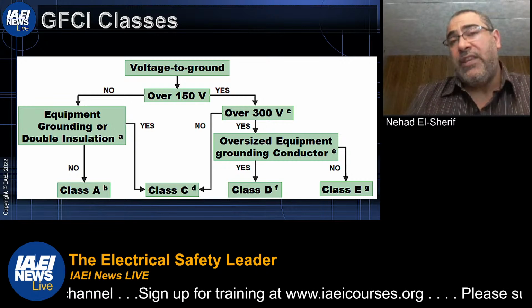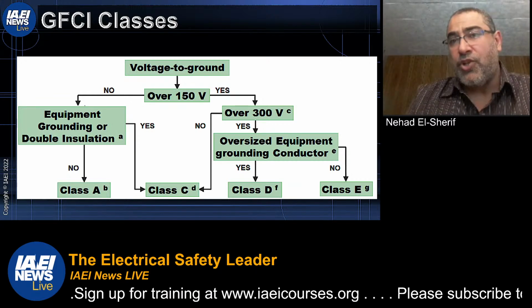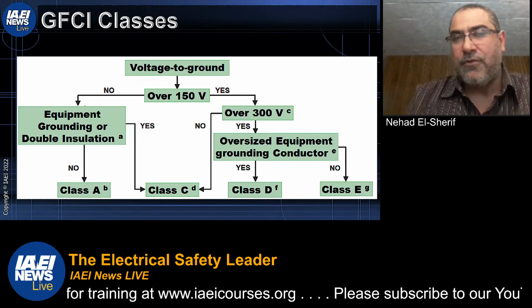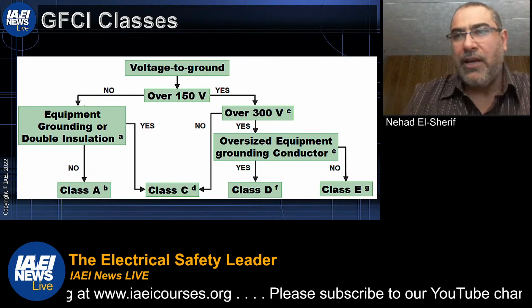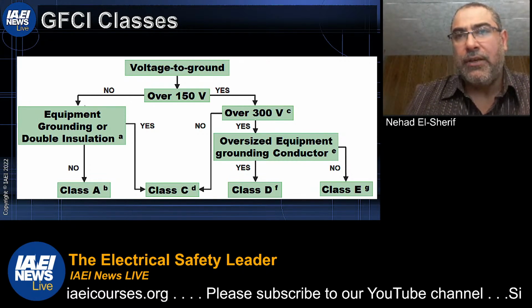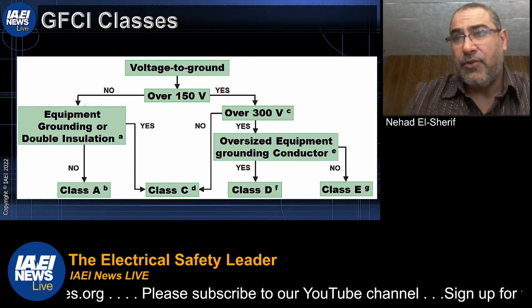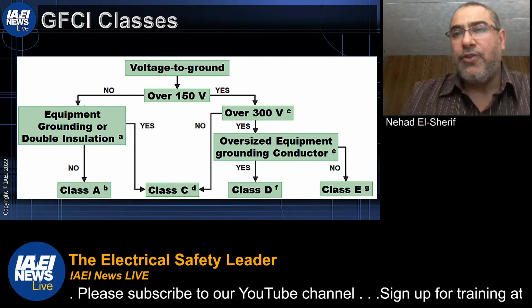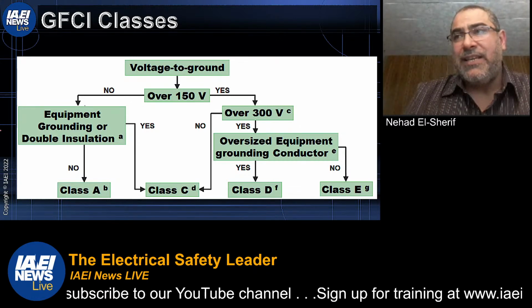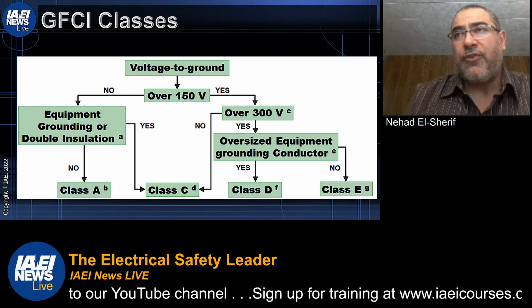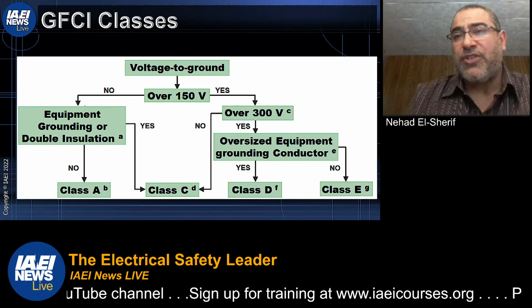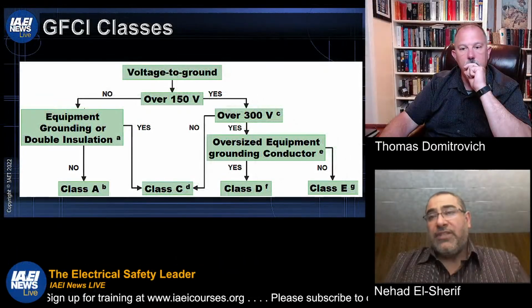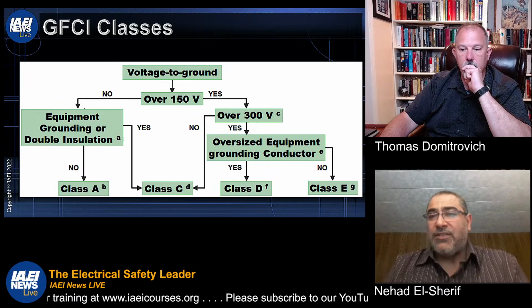But if the equipment grounding conductor is not oversized, which is probably the case for, I would say, 99% of the facilities we have, then you'd need to use a Class E. Class E is what UL refers to as the ultra fast tripping, because it trips much faster than Class D. So you don't oversize your grounding, but you trip much, much faster than Class D.